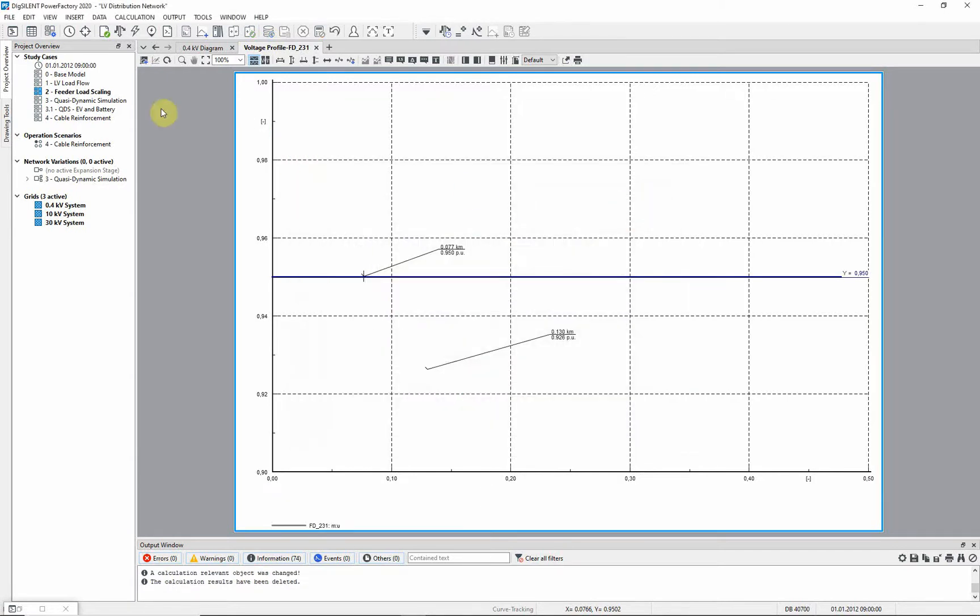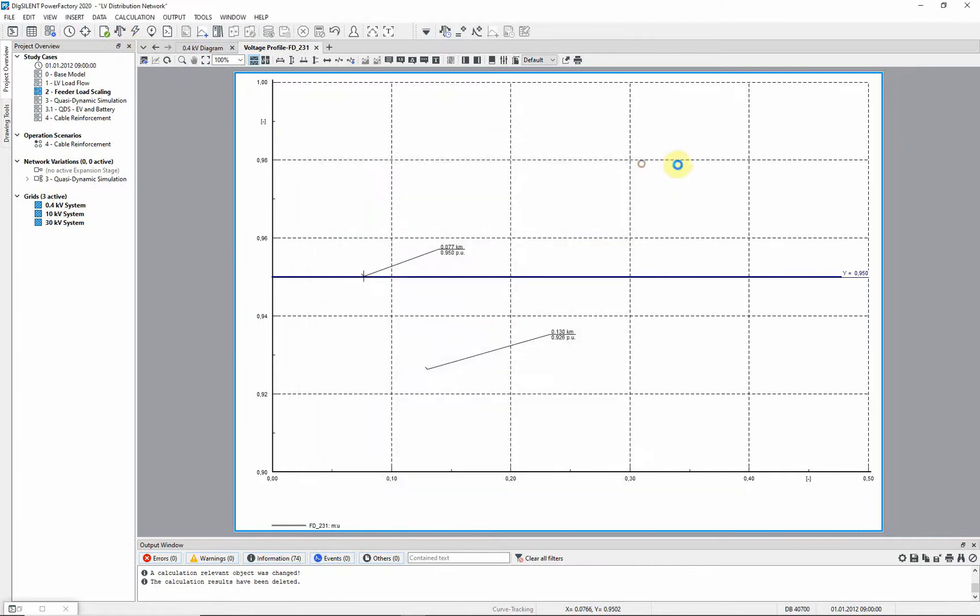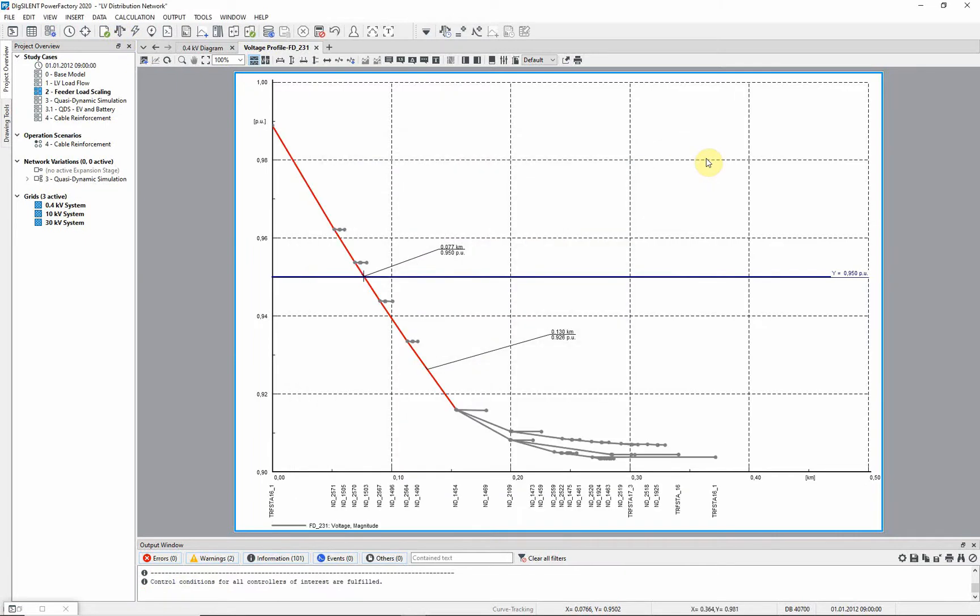Rerun the load flow. Notice that the voltage profile has not changed. This is because we have not enabled load scaling on any of the individual loads contained in the feeder.